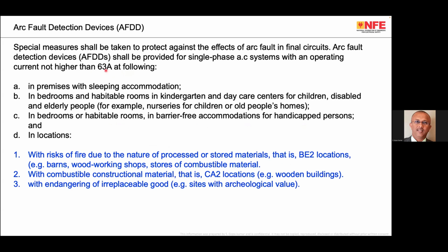First of all, AFDD is an additional protective device which has to be used not in every circuit, but in some circuit where a chance of fire could kill people. If you try to put AFDD in every circuit, it will create only nuisance tripping. Two years back, one international company, for their warehouse, installed AFDD in almost all the circuits. After 6 months, they realized that due to the quality of workmanship in our country, due to poor terminations, arcings happen and the AFDDs started tripping.